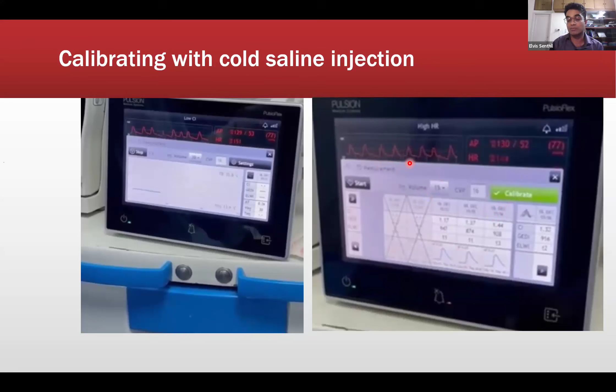So if you do it 3 times, up to 5 times, you will average that and you will get a cardiac output. Now this is calibrated to the pulse wave which is going through the arterial line, and the machine decides, okay, this shape of the pulse wave is equal to this much cardiac output. So if the next wave is smaller, that's a lower cardiac output and so on.